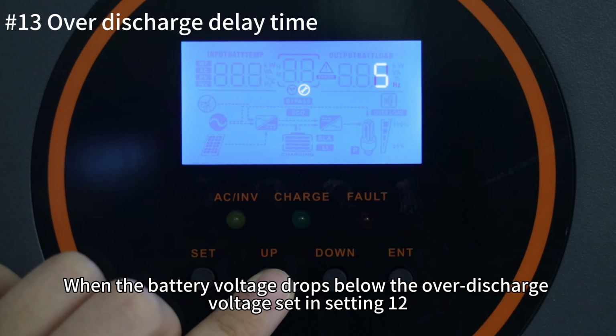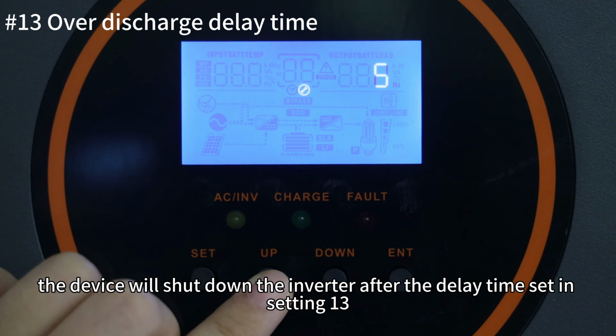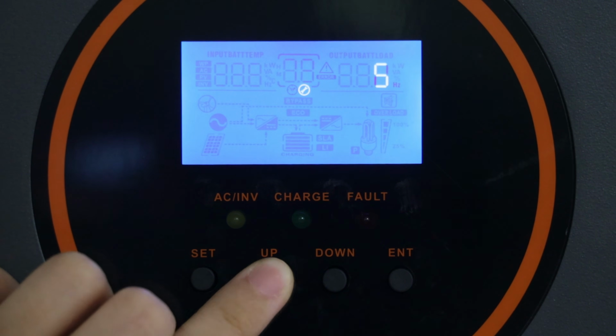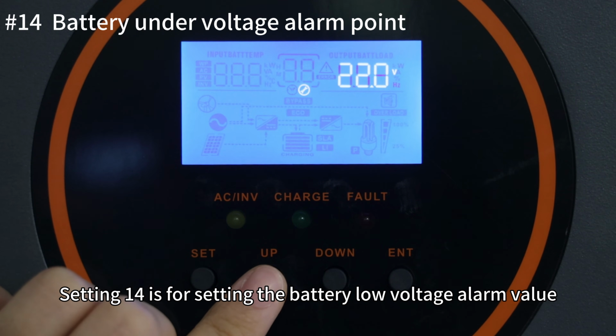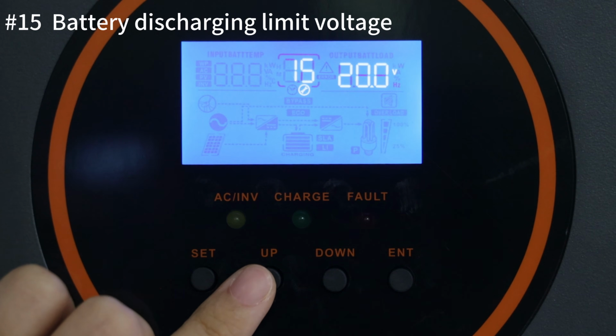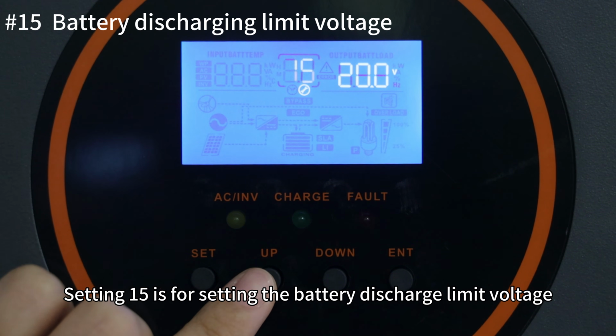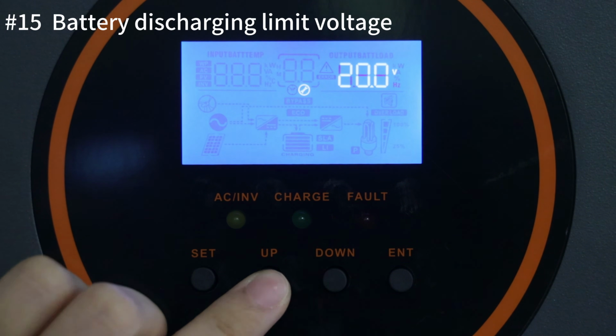When the battery voltage drops below the over-discharge voltage set in setting 12, the device will shut down the inverter after the delay time set in setting 13. Setting 14 is for setting the battery low voltage alarm value. Setting 15 is for setting the battery discharge limit voltage.